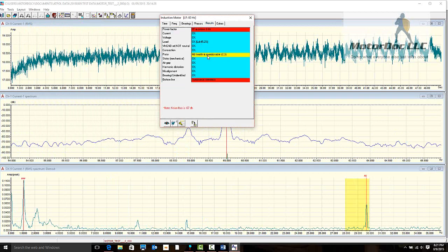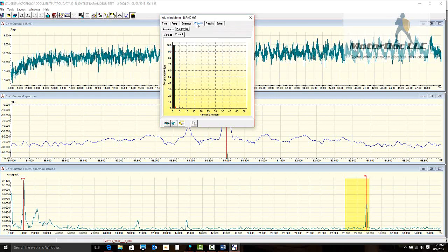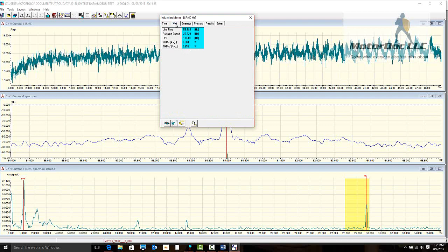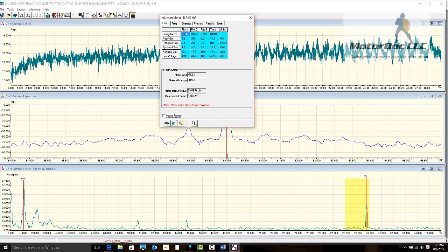It says rotor bar health is questionable. Yes, because I have definite pole pass frequency sidebands. There's my harmonics. Bearings are still okay. Here's the operating frequencies, including the calculated pole pass frequency. And there we are with a running current of about 17 amps. It has calculated my motor load at 45.2%. It has calculated the efficiency at this point at 90.5%. It's also providing me with specific information.